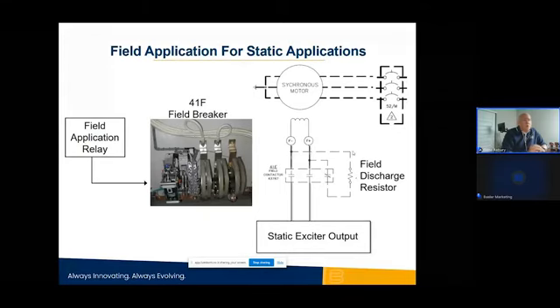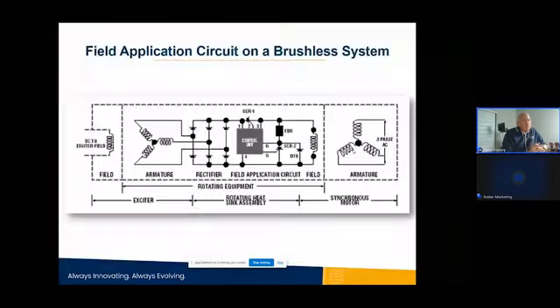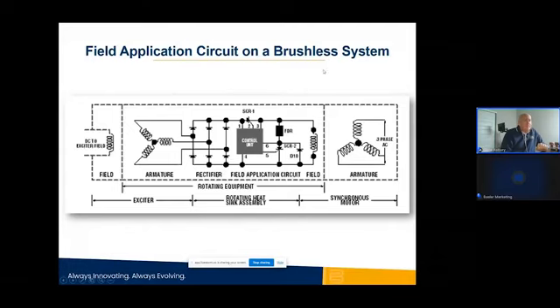In a brushless synchronous motor, it's a little bit different, but the effects are the same. So now you've got your rotating exciter in the middle box. You've got your motor in the box to the right, and then you've got the field of the rotor in the box to your left. And our controls would be supplying excitation to the exciter field. And now you've got a control unit within the brushless exciter.